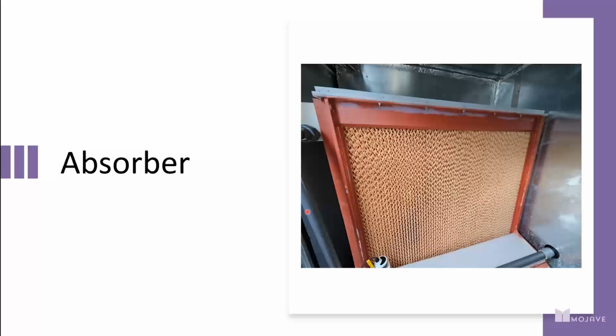Now, we've looked at face velocity, flow rate of air, flow rate of desiccant, surface tension, media, and geometry to all determine and test out to single-digit parts per billion, with a B, that we have basically created this closed loop system where desiccant is not being pulled out of this media into the airstream. We do have a white paper detailing that process, but it is effectively closed loop in the sense that nothing comes out of this media. Then to finalize that thought, we do have a 3x safety factor on face velocity as well with our system to ensure that we don't ever put ourselves and our equipment at risk of pulling desiccant out of this media into the airstream.